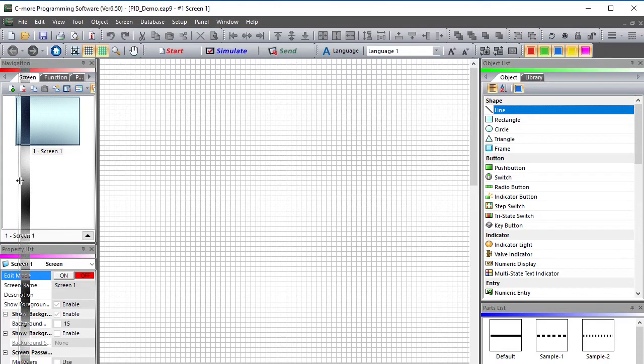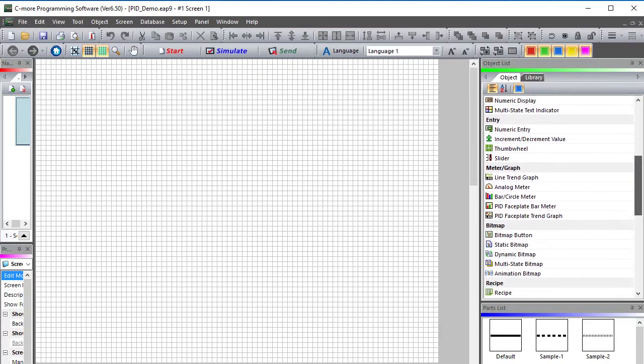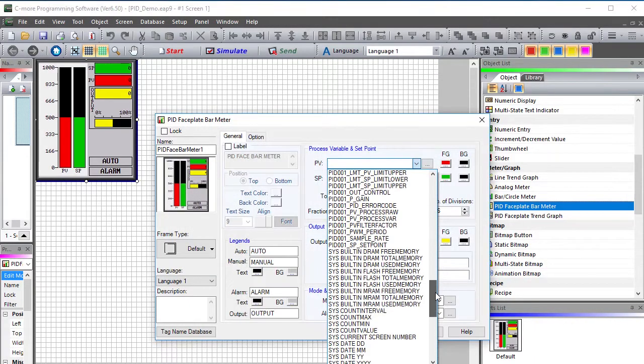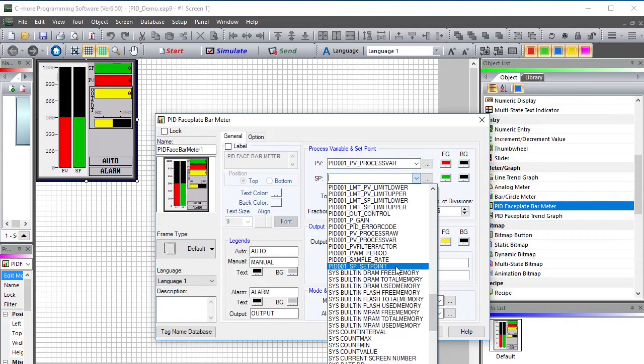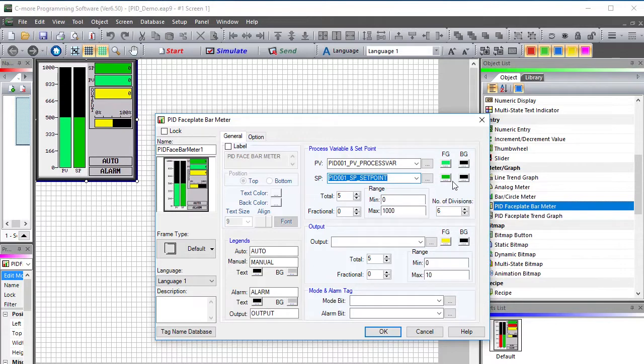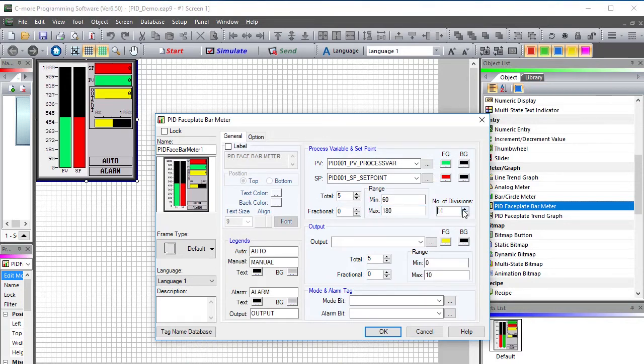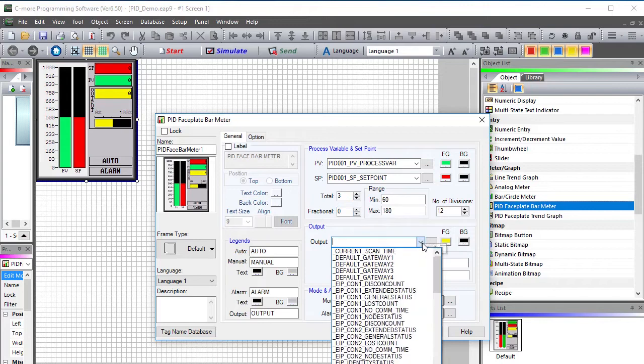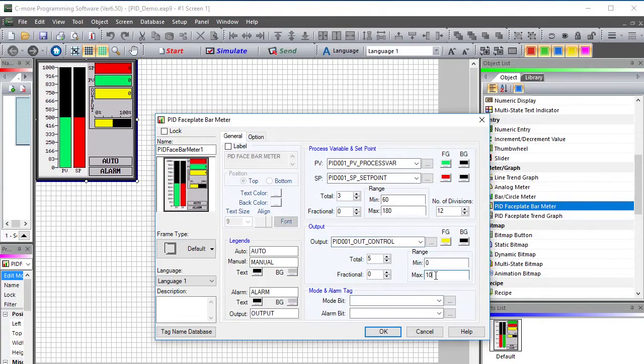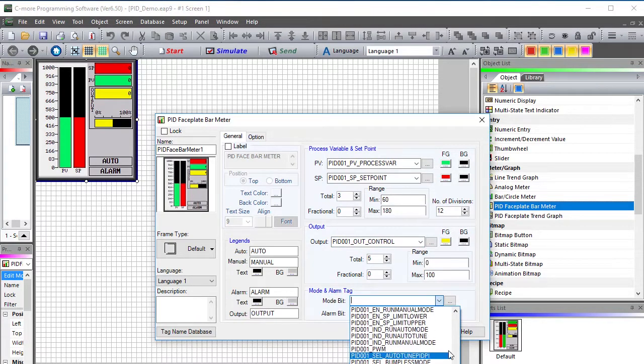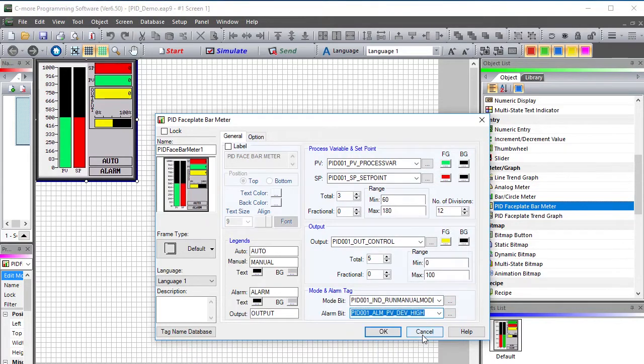I'm going to scrunch the app up a little bit so we can see the full HMI screen on our display. Now we just scroll down to the PID bar graph and drop it on the screen. Our process variable is this tag, our setpoint is this tag, and I'm going to make the process variable green and the setpoint red so they match the PID monitor we've been using. We know our process variable will be between room temperature and around 170 degrees, so I'll put 60 to 180 in here with 12 divisions to give us evenly spaced tick marks on the bar graph. We only need 3 digits and no fractional digits for the tick mark labels. Our output is this tag and its range is 0 to 100%. The auto/manual mode indicator is selected with this tag, and we can put any alarm bit we want here.